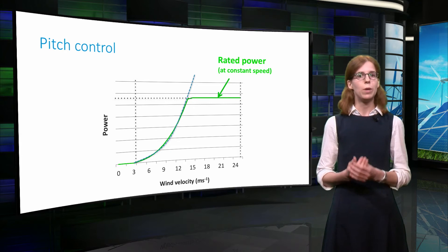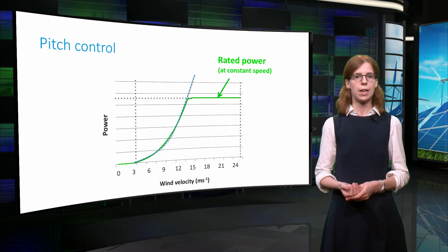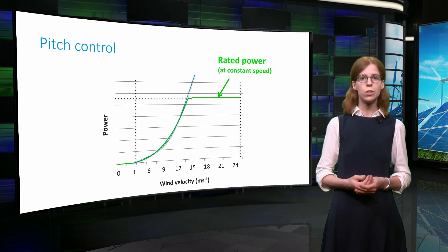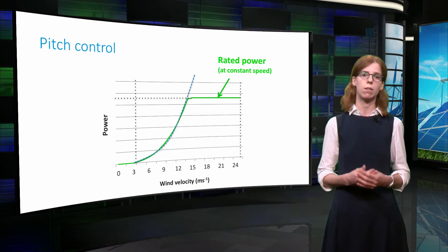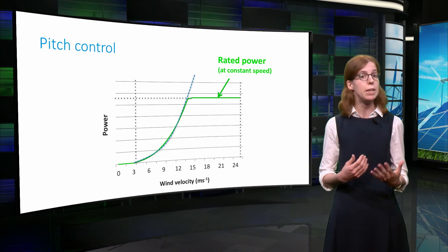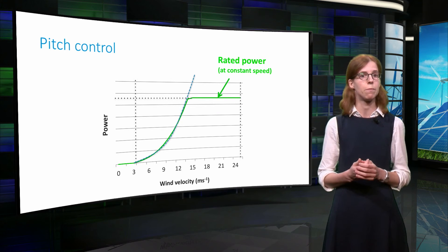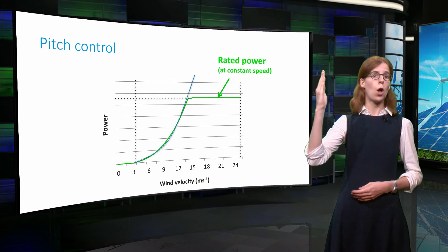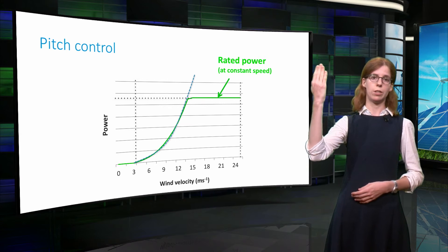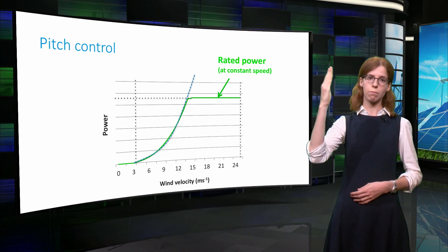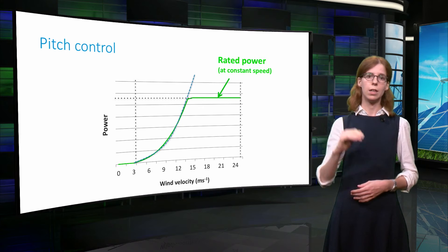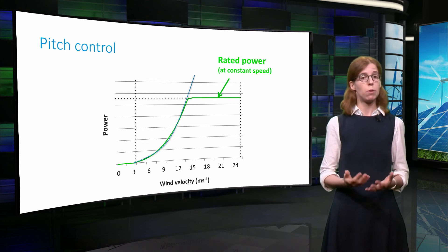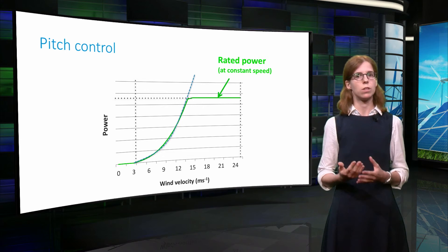Eventually, when rated power is attained, the power is kept constant by turning the blades along their axis, that is by pitching them. If my arm is the blade, a pitch rotation is this motion. This is called pitch control and is performed at constant torque.